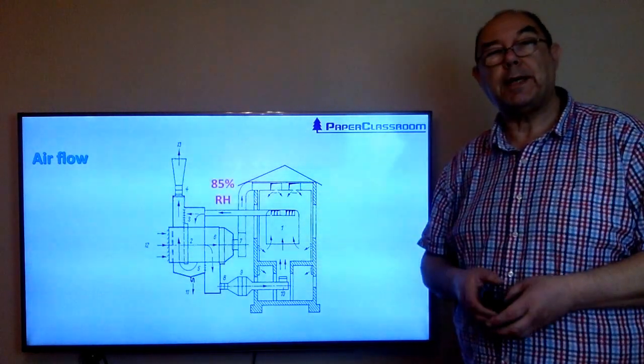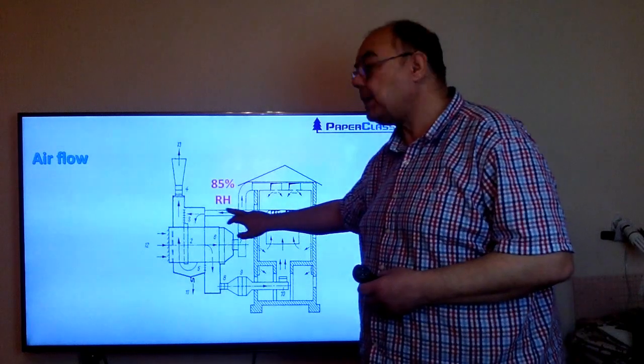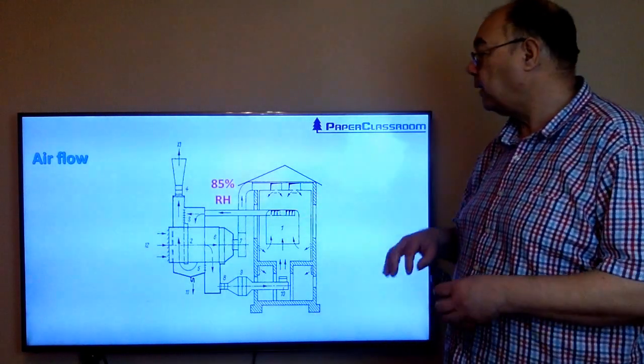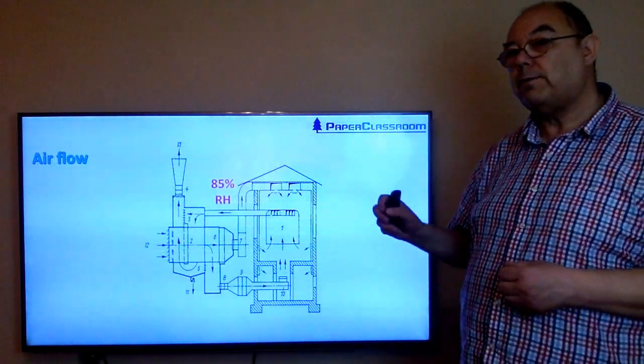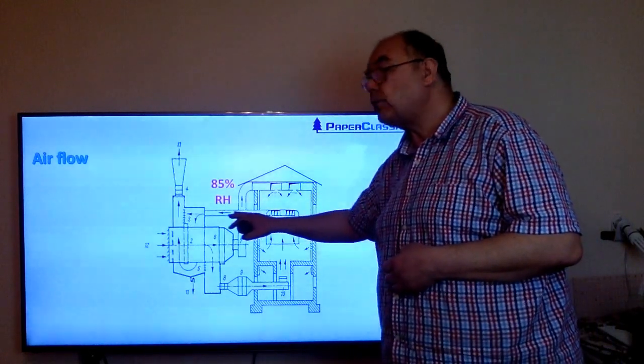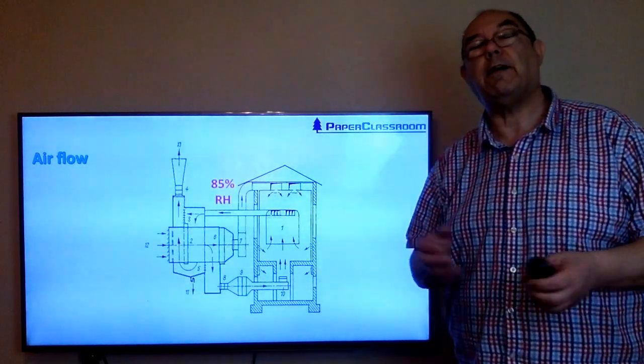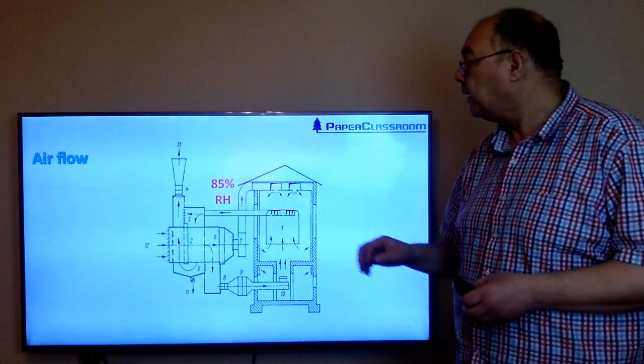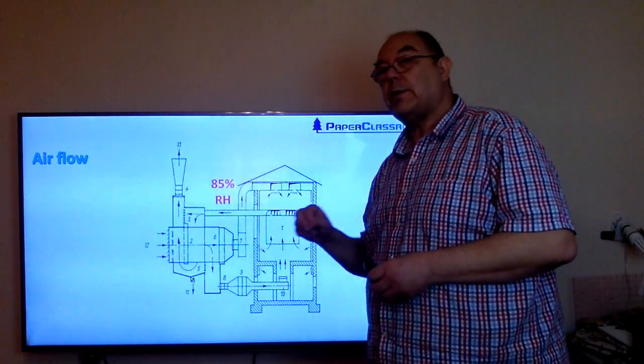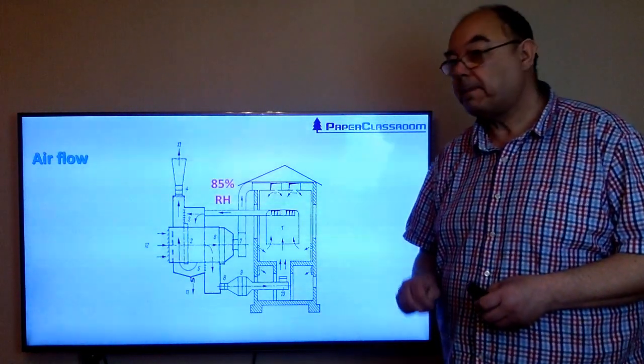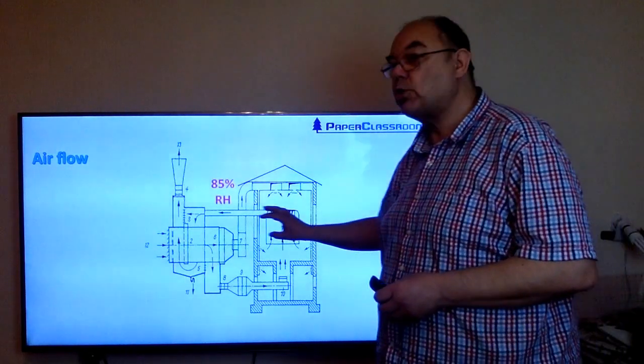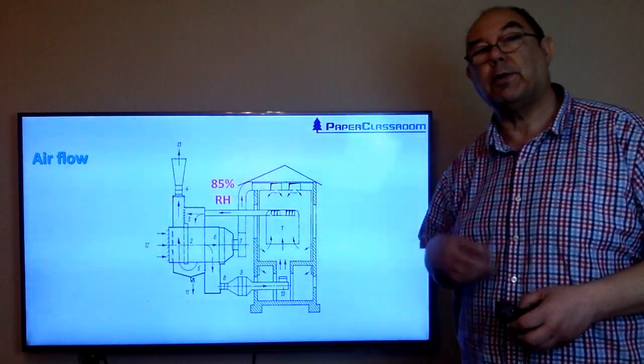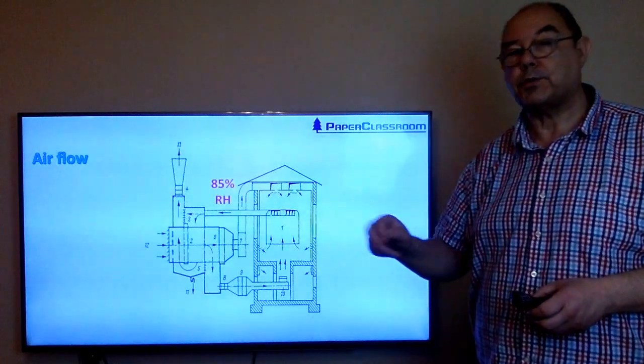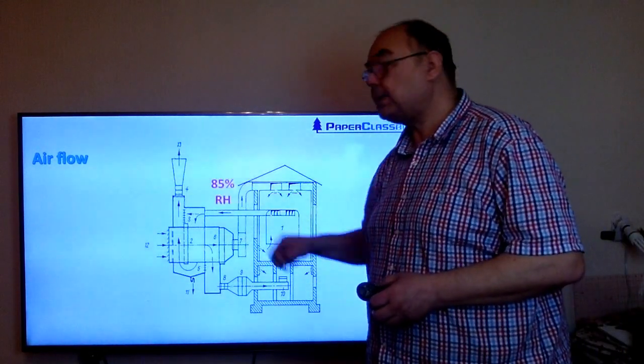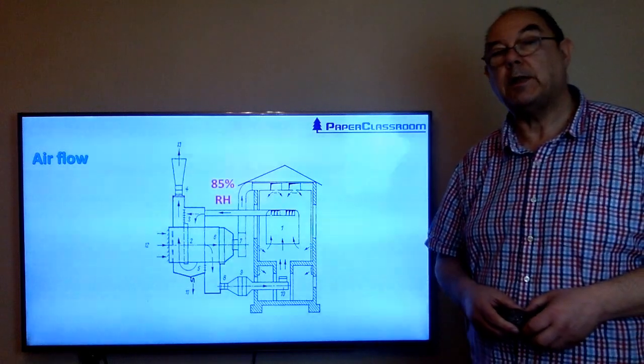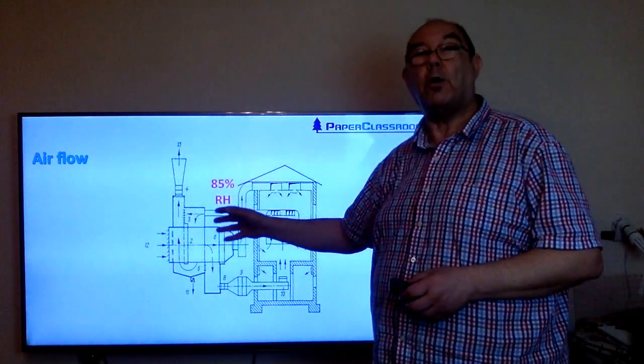And another important thing is measuring the humidity of the air coming out. And it's generally accepted that the perfect humidity for air coming out of the system should be round about 85% relative humidity. If the value is lower than 85%, that really means you're pushing too much air through, and therefore you're wasting money on electricity with the fans. If the relative humidity is greater than 85%, that means that the airflow is not good enough.